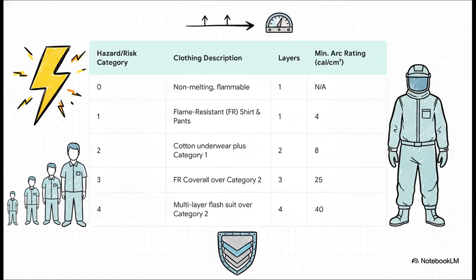So you take that incident energy number and use a table, like this one from NFPA 70E, to figure out what level of protection you need. You can see as the minimum arc rating climbs from 4 calories to 8, up to 25, and then all the way to 40, the gear gets more and more serious - more layers, more coverage, the whole nine yards.